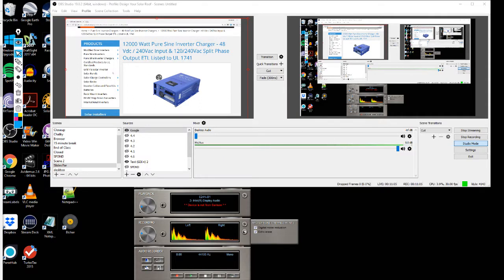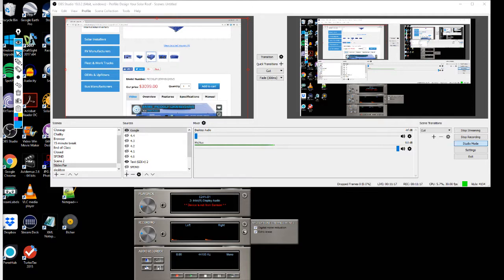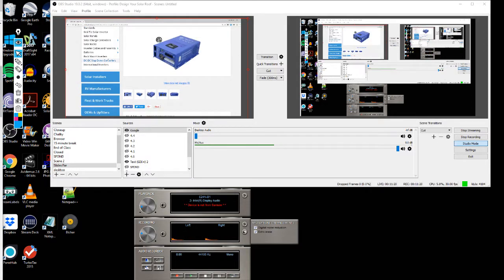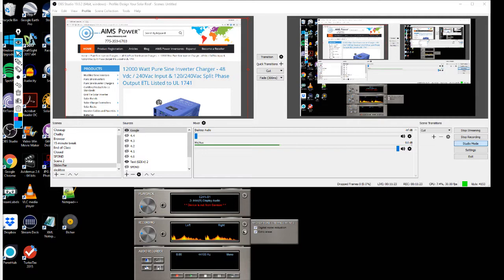So I guess what I've done in this cost example on the slide here is said, okay, we're going to buy the $3,000 inverter, and then we're also going to put 2 big charge controllers. And so our total inverter system, the 2 large charge controllers plus the AIMS inverter, is going to be a $5,000 system that's going to give us 12 kilowatts of inverter capacity.